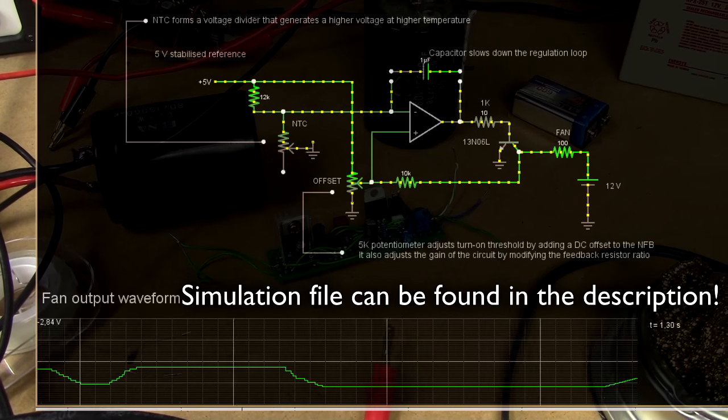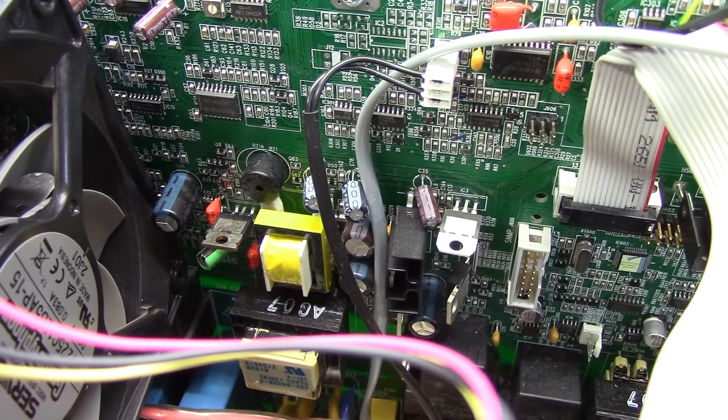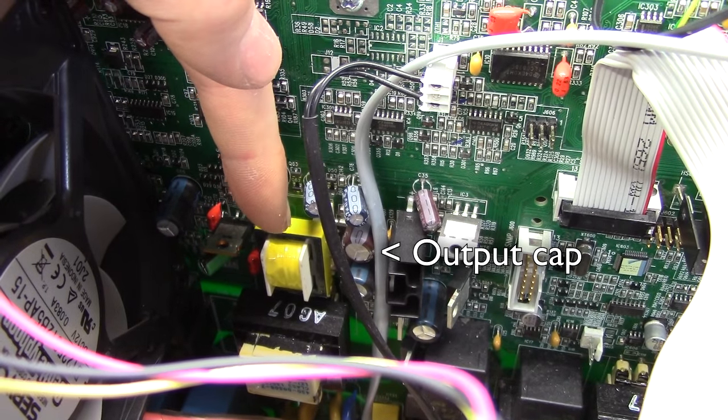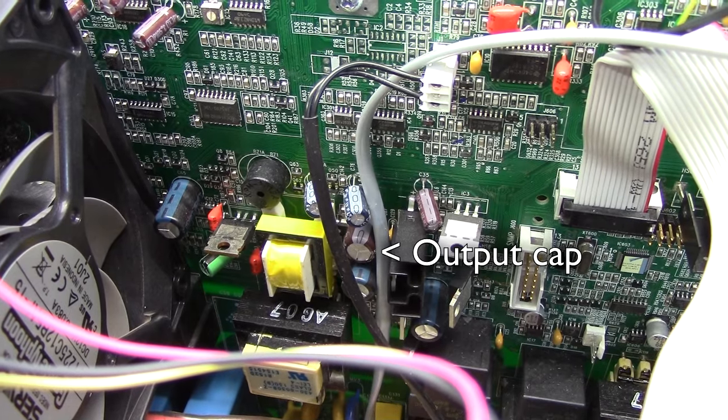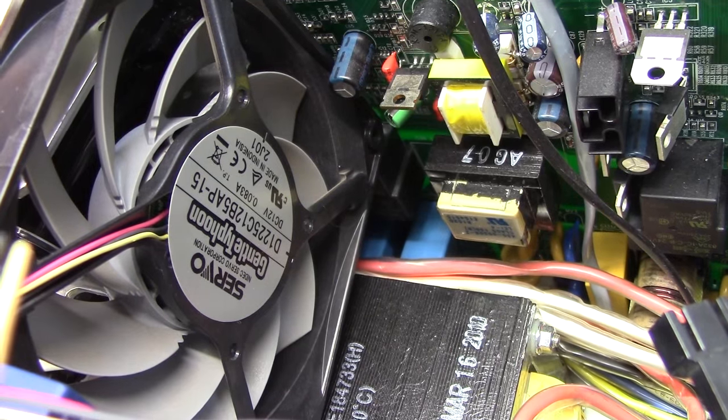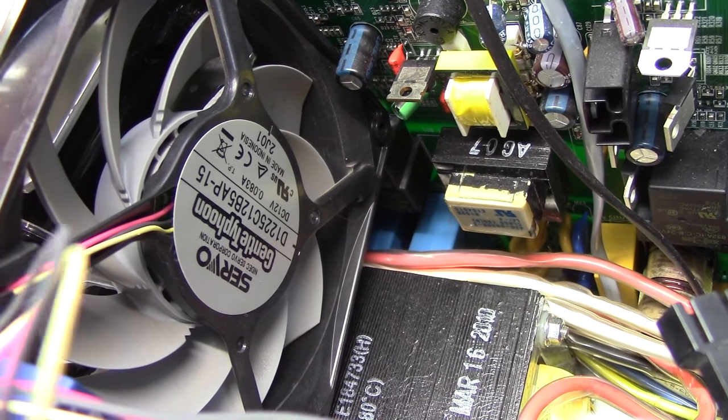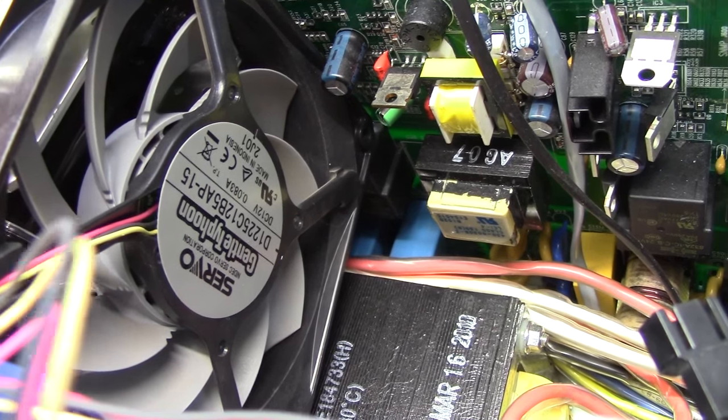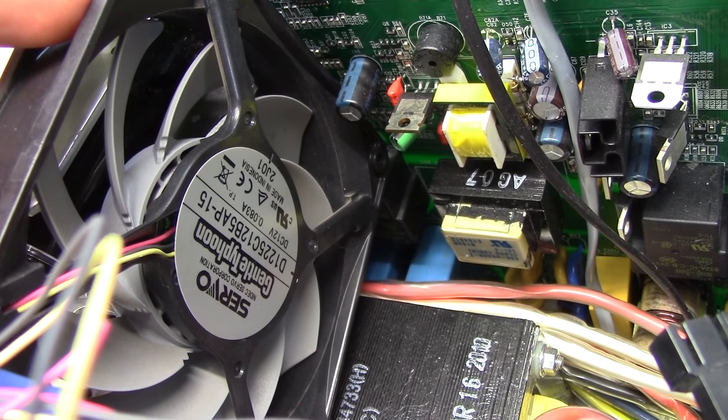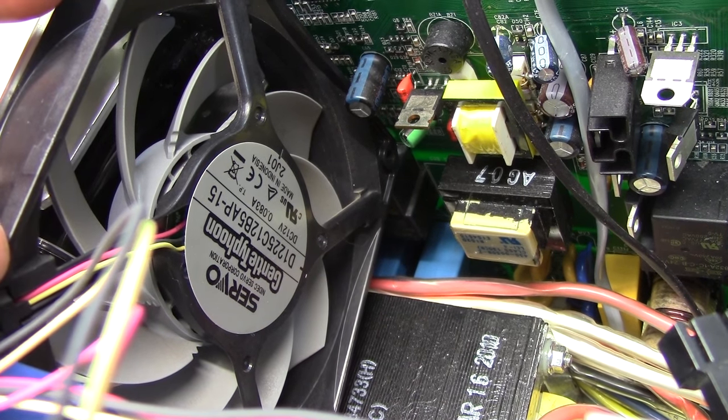This enables the fans to basically turn off at low temperature and spin up rather quickly when the load on the unit changes, for instance, it goes into battery powered mode after being on grid. I'm planning to run this off the internal 12V rail of the UPS, which should be this little switch mode power supply in here.